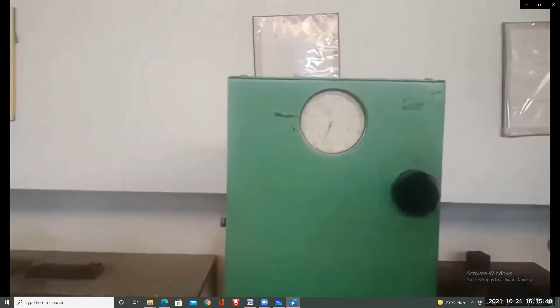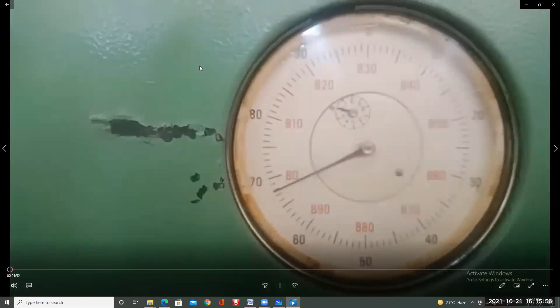Then switch on the machine. Once the machine is switched on, raise the anvil. Once it touches the indenter and specimen, I will set the minor load. I will rotate the anvil, and the smaller indicator will come slowly till the smaller needle touches the red dot in the smaller dial gauge. That means the minor load, that is 250 kg, is acting on the specimen.